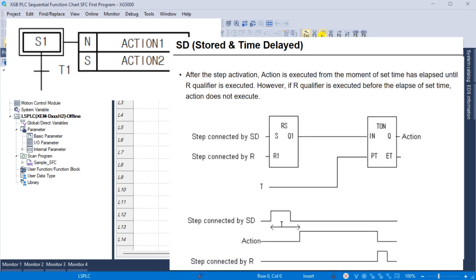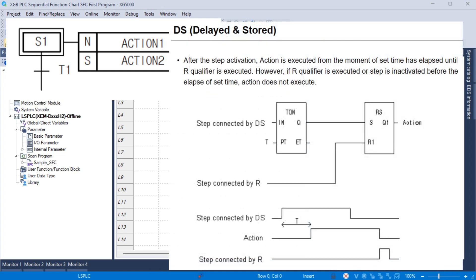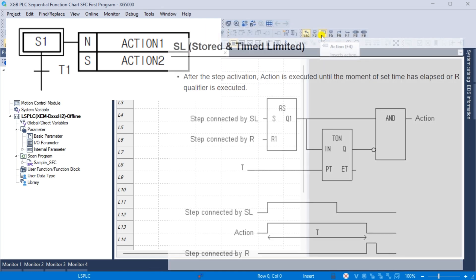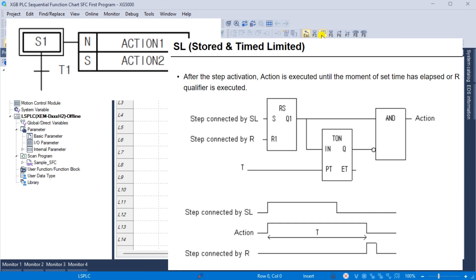SD, stored and time delay: after the step activation, action is executed from the moment the set time elapses until the R qualifier is executed. However, if the R qualifier is executed before the elapsed set time, the action does not execute. DS, delayed and stored: after step activation, action executes from the moment the set time elapses until the R qualifier is executed; if R is executed or the step is inactive before the set time elapses, the action does not execute. SL, stored and time limited: after step activation, action is executed until the set time has elapsed or the R qualifier is executed.